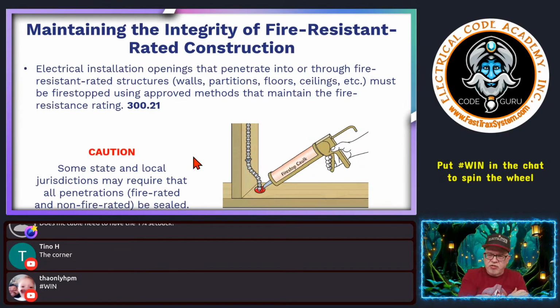The AHJs might call it out on the electrical. It is 300.21 if it's a fire rated assembly, and typically top plates and bottom plates would require those to be sealed. But again, check with your local jurisdiction. There's the foam, the Great Stuff orange we used to use. I can go around and hit the entire house and be done with it, that type of thing. But this is just a fire caulk, probably from a 3M or Hilti or something like that. So you have to maintain it, that type of thing.